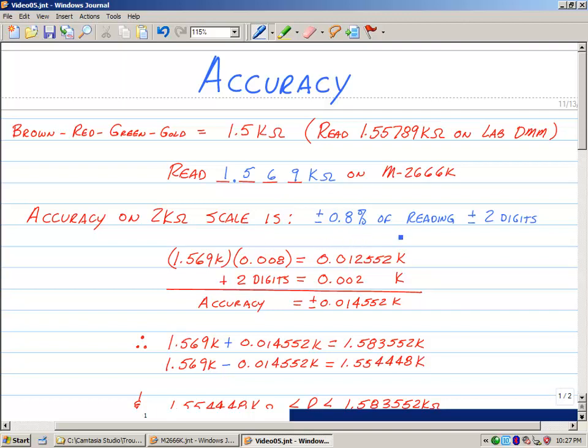If we take 1.569k and multiply it by 0.008 which is the 0.8 percent at this value in k ohms, which is about 12.552 ohms. If you add two digits what that means is that you take all the places here and you put 0002. So wherever the decimal point is just leave it there and you put a two in the last place and this is k ohms leave the k here. Now when you add those two numbers together you get 0.014552k. So if you take that number and add it to the reading and subtract it from the reading that becomes the range of values that you actually have for this resistor given the meter.